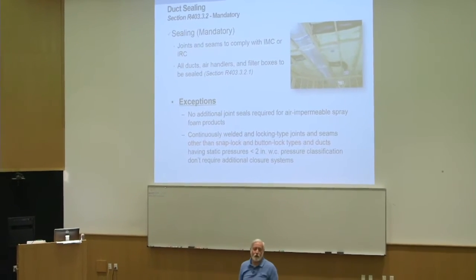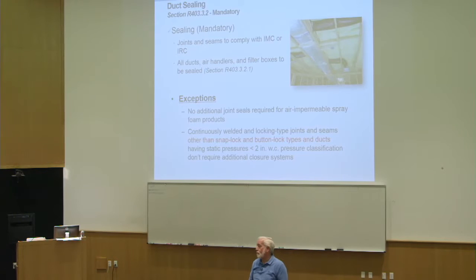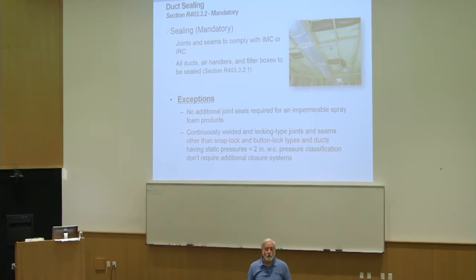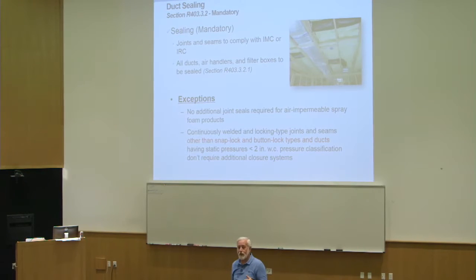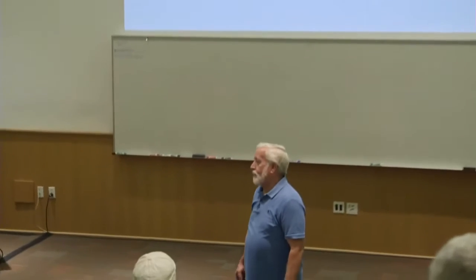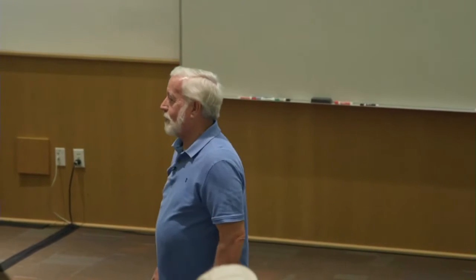The 15 code says that you're supposed to seal the longitudinal or the long joints on snap lock duct. That would include 6-inch pipe and all your snap lock rectangular duct. If the machine isn't adjusted right, you can get a fair amount of leakage out of that snap lock. With 6-inch pipe, I'd actually like to put a couple hundred feet together and take it up to, well, 25 is your test pressure, but I'd like to take it up to 50 or even 75 and see how much leaks in the snap lock if we sealed everything else. That actually goes away, I think in the 18 or 21, I can't remember.